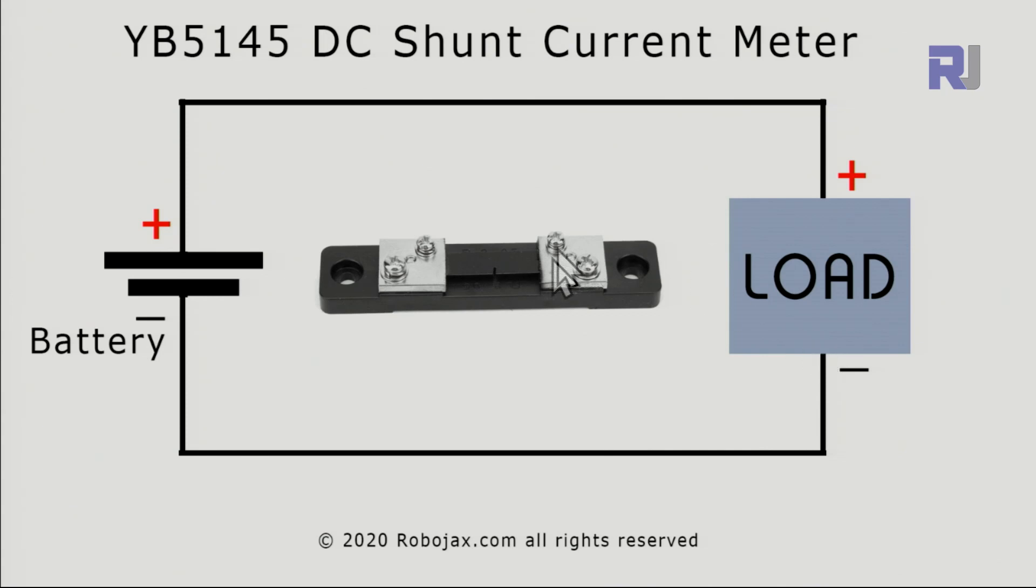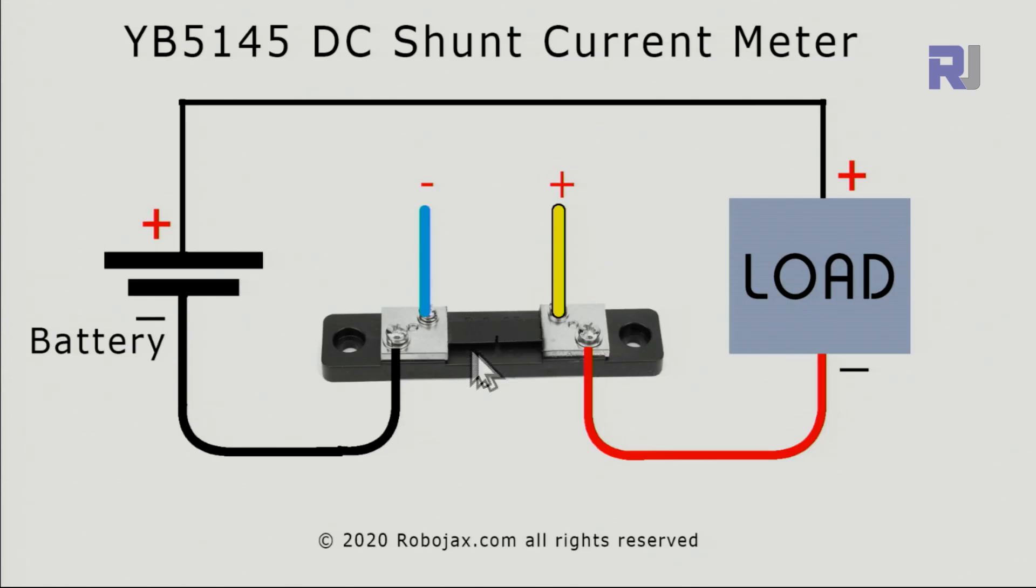Let me now explain the wiring. This is your shunt resistor. We have a meter, you have a battery and you have a load. This is without measuring the current - you will connect it like that. But to measure the current you will put a shunt resistor in series with the load. The negative comes and passes through this shunt resistor and we have a voltage that appears proportional to the current where we can measure it using these two blue and yellow wires connected to the meter.